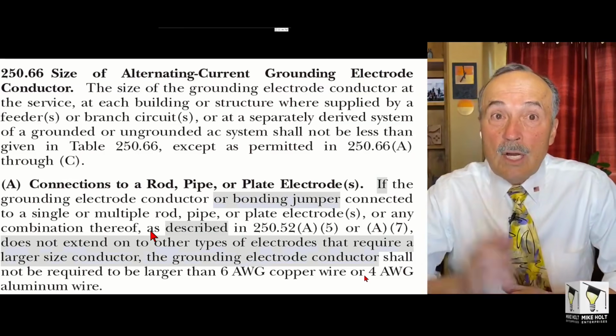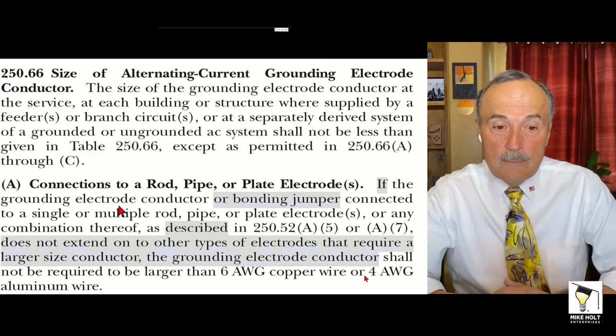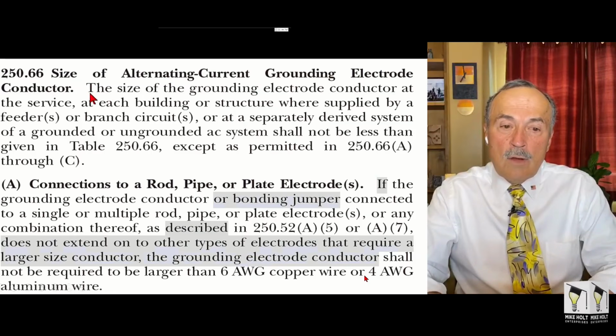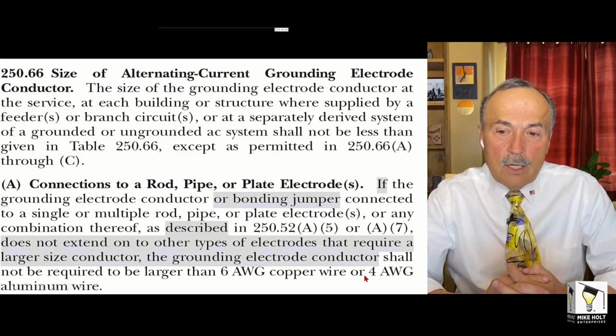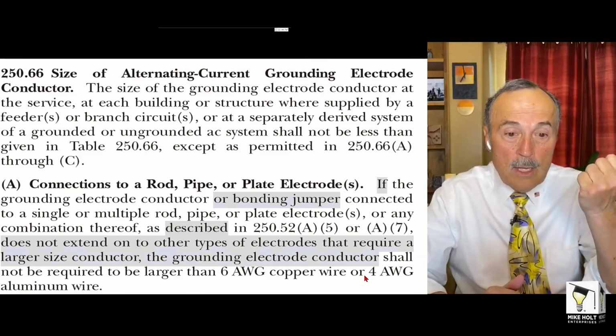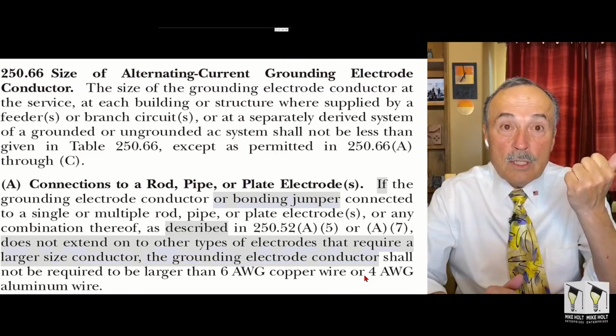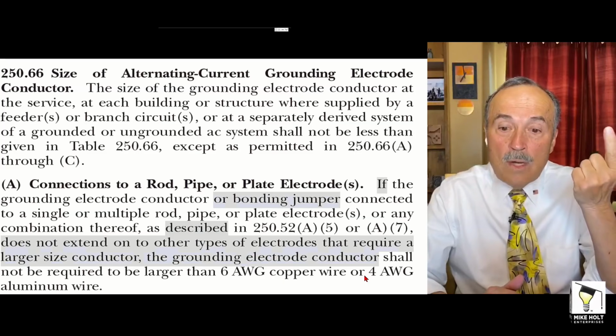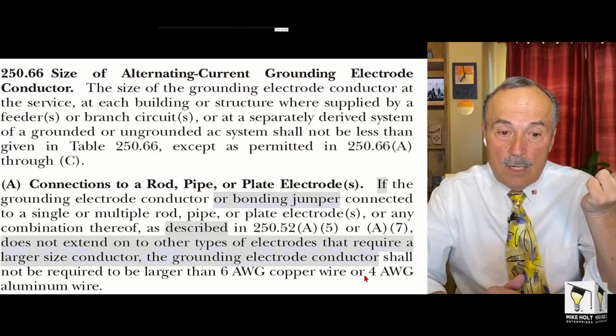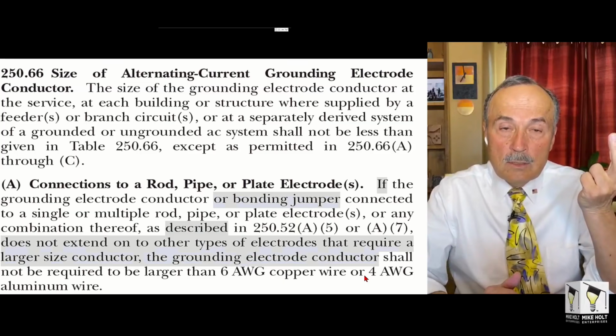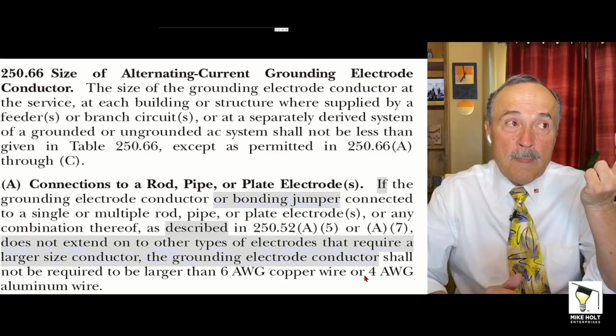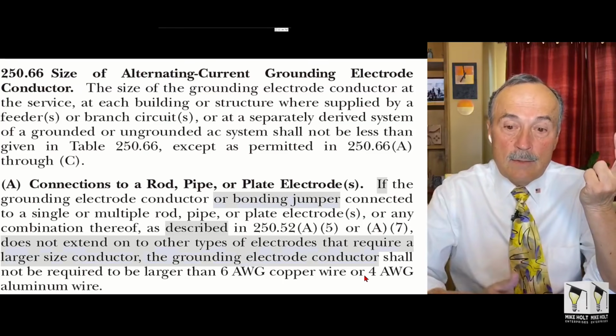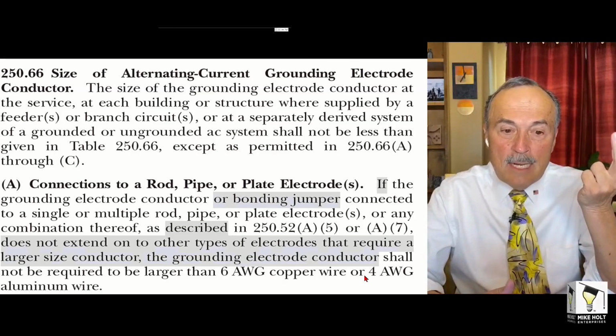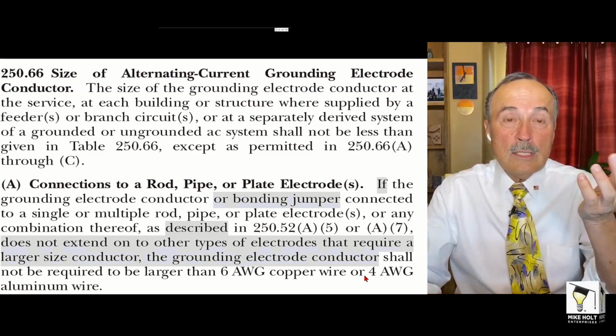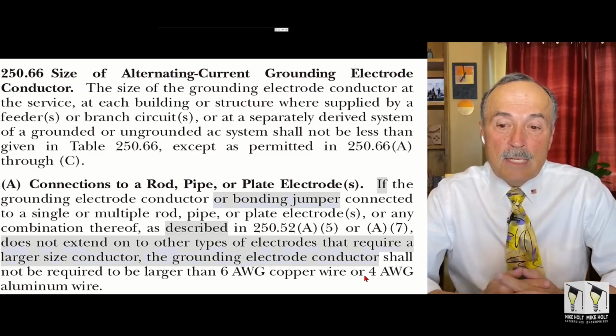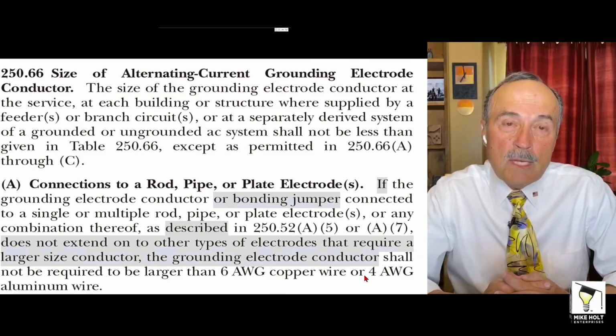So where you need a grounding electrode conductor, you go to 250.66 to size that conductor. Let's read it. Size of the alternating current grounding electrode conductor. The size of the grounding electrode conductor at the service, 250.24, at each building or structure supplied by a feeder or branch circuit, 250.32, or at separately derived systems, 250.30, or ungrounded systems. See, ungrounded systems, you need a grounding electrode conductor to go off of the enclosure. And that's going to be 250.30 also, except it's B. Shall not be less than given in the table. So you go to the table. Except as permitted in 250.66 A through C. That's where people screw up.